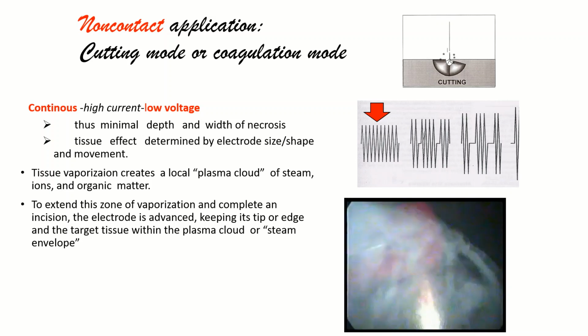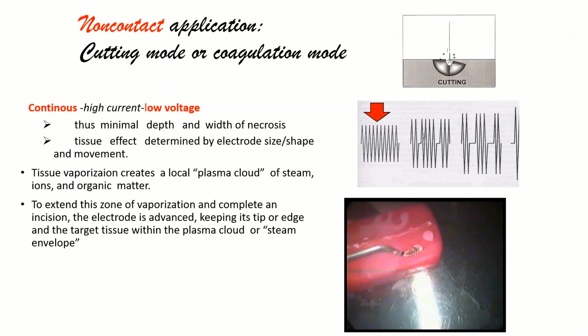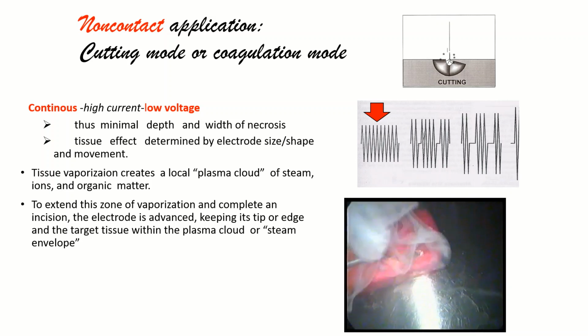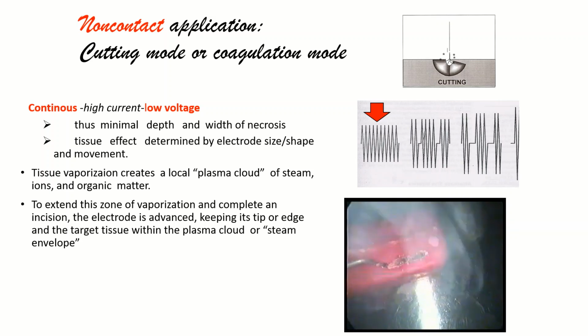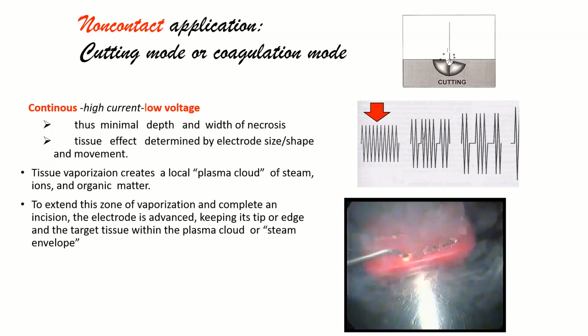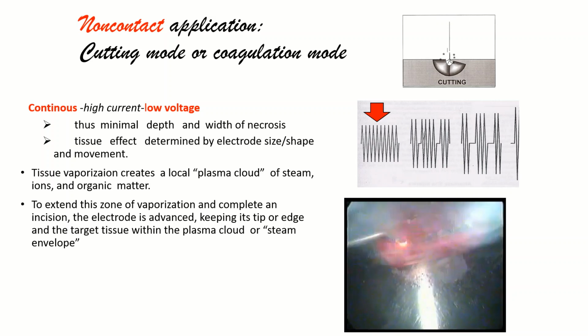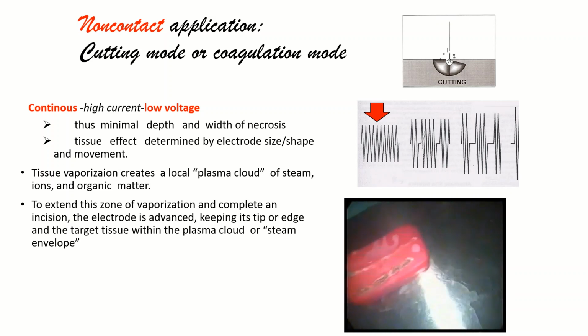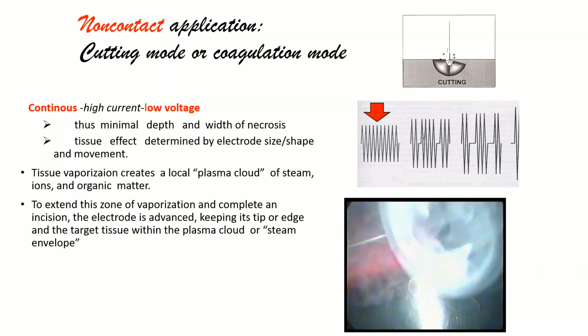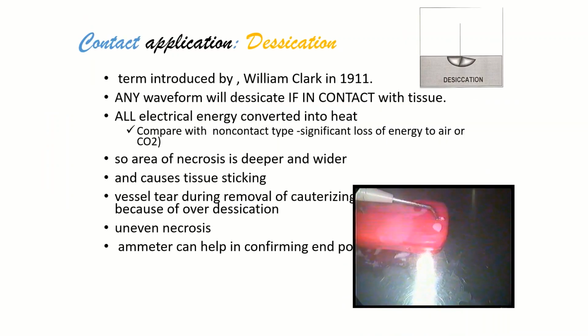Now let's see this once again. So that cloud and a lot of smoke. So in this zone of vaporization you have to keep the probe inside the zone so that you can complete the cutting or the coagulation maneuver. This is known as the steam envelope. Now, that was the non-contact application we're talking about, which can be a pure cutting or a pure coagulation mode. Now, let's see what the contact application is. We said earlier that this is the most common form of application and the most common form used by surgeons.